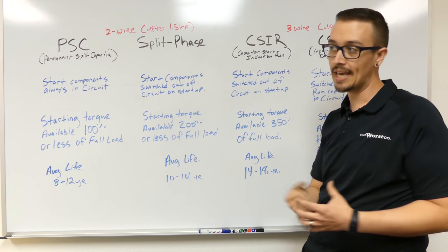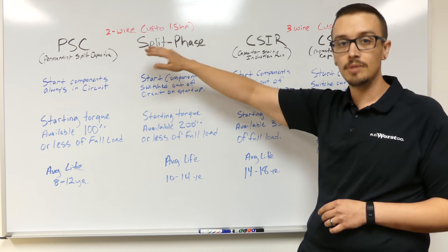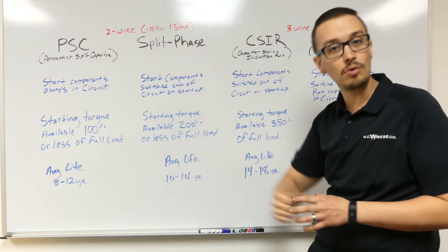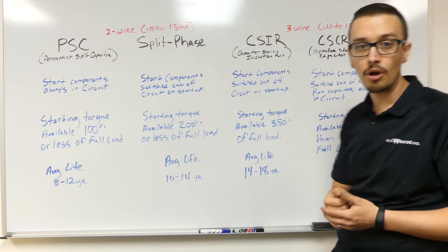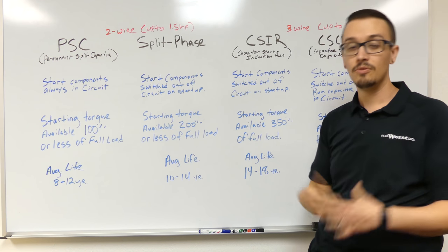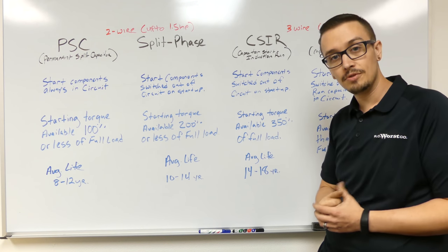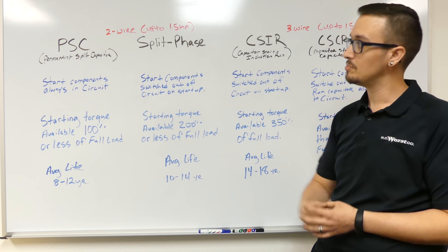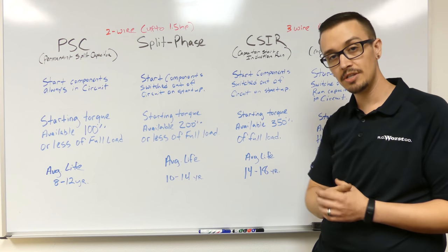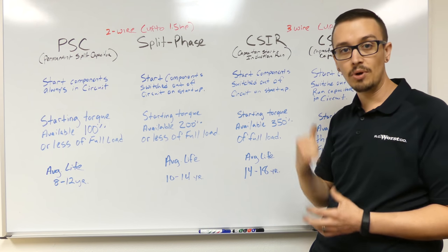The notable differences right out the gate is two wire are limited to up to one and a half horsepower. Three wire, you can go up to 15 horsepower before you're having to go with a three phase. So let's focus on two wire for just a minute, talk about some of the differences between PSC and split phase motors, and then we'll jump right into three wire.